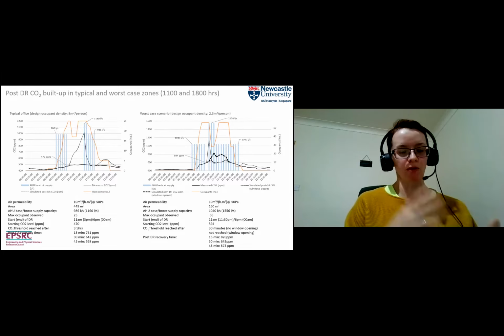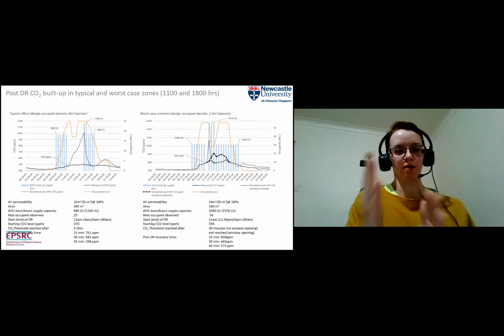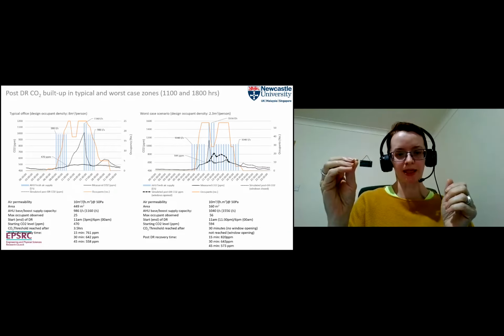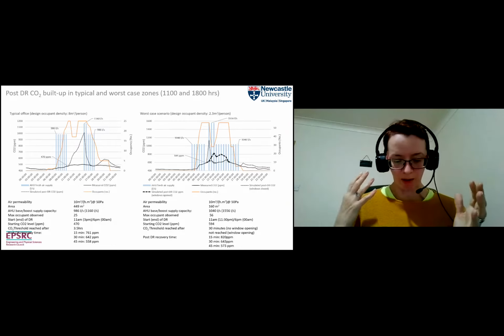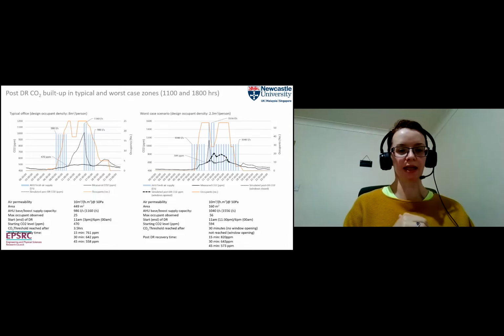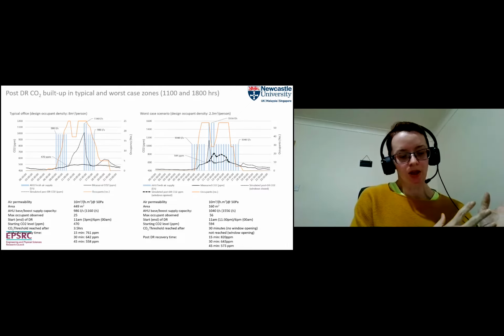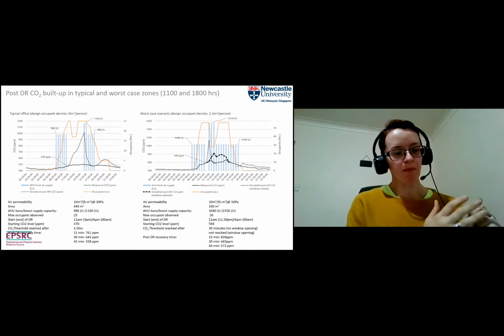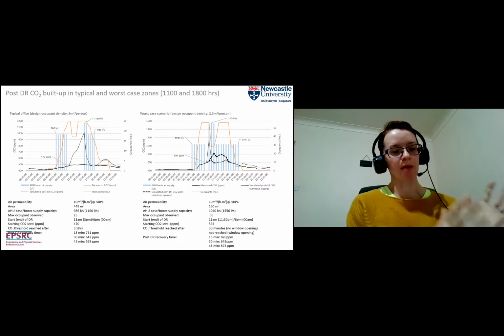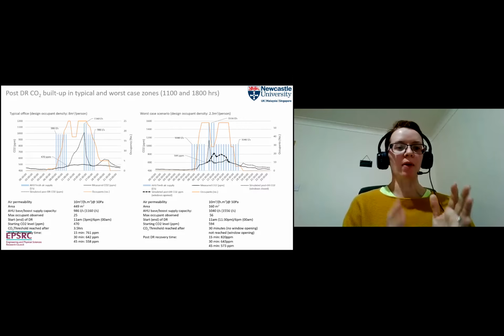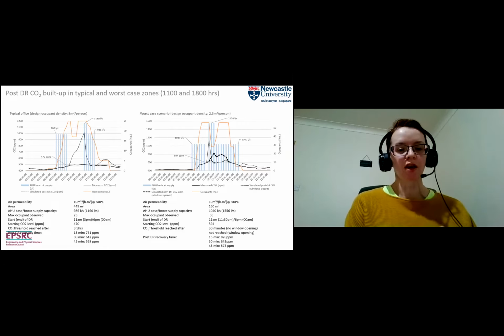So we've got blue bars showing that the ventilation is on and the air handling units are on. Then when the air handling units are off and there's no blue bars and we've got some occupancy, which the orange line is showing, then our CO2 level gradually increases in the space until it reaches this threshold where we can't override the system, the air handling unit kicks back in. So we've got some opportunity to save electricity at times of peak electricity demand by turning the air handling units off. But our typical office shows that we can really only do that for 4 or 5 hours in terms of when the threshold is reached. So in a typical office space, the CO2 threshold is reached after 3.5 hours.